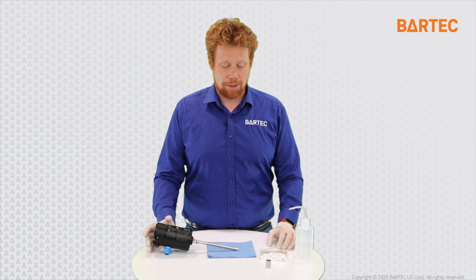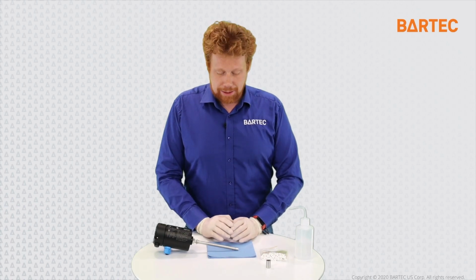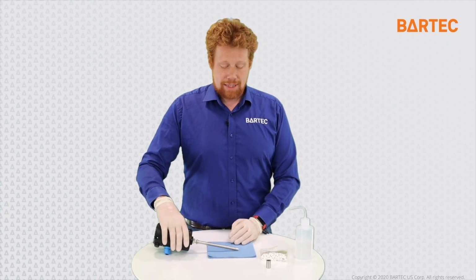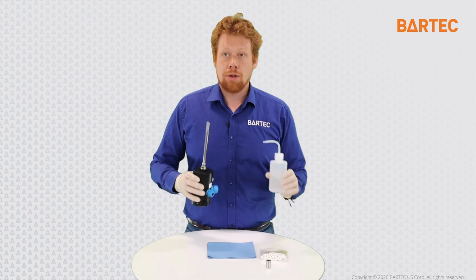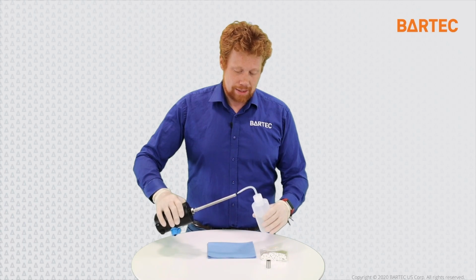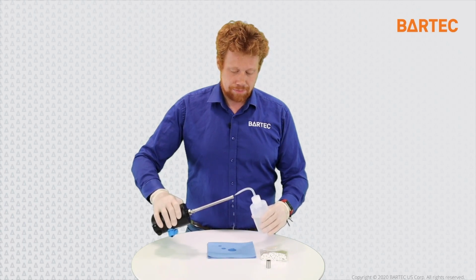Before handling any chemicals, please refer to the requirements of your health, safety, and environment policy in your company to make sure that the handling of the chemicals is done according to the requirements of your company. In my case, I will be putting on gloves before touching the isopropyl alcohol. Now, how do you clean the probe? As I said, it's a relatively simple process. Once the probe is out of the process, take your IPA and wet the tip of the probe.